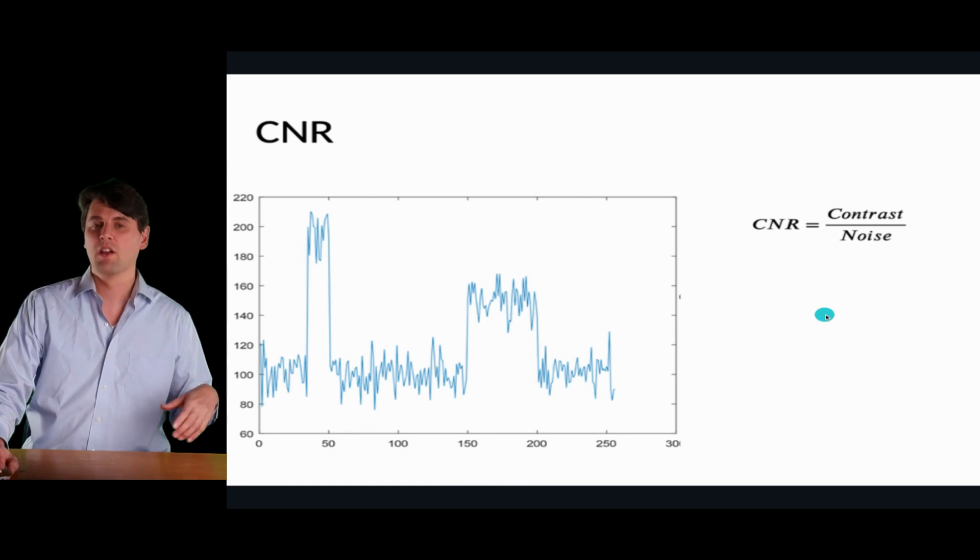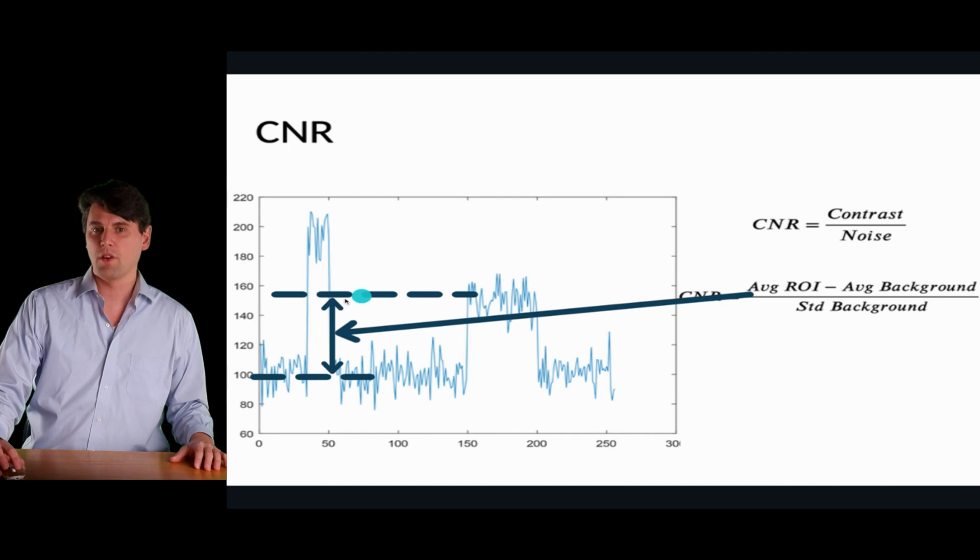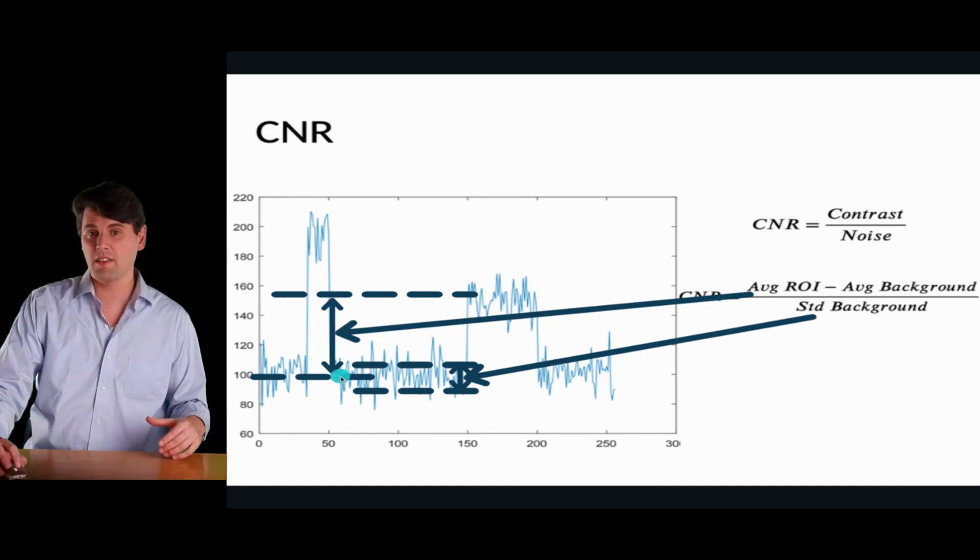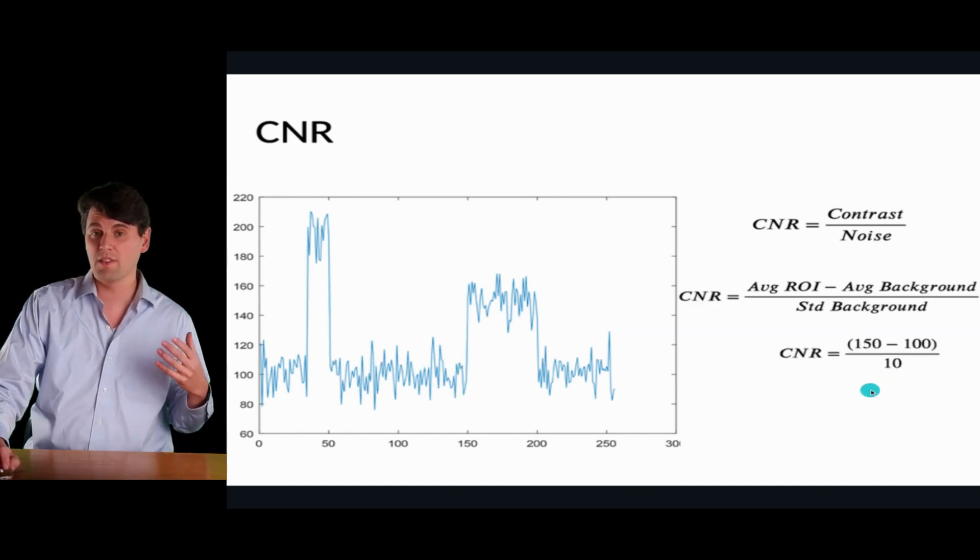Then the question is, what would be the contrast-to-noise? So again, with the exact same data, now with contrast, we're actually more concerned with the ability of the system to differentiate this object with respect to the background. So now we want to look at the difference between the signal. So the contrast is the difference between the signal here and here. And then again, contrast-to-noise, we're going to be dividing by that standard deviation of the noise in the background. Now the contrast-to-noise here is going to be, this is about 150, this is about 100. So the contrast is about 50 here. And then the noise value is the same there of about 10. So the contrast-to-noise is going to be 50 divided by 10 or about 5.